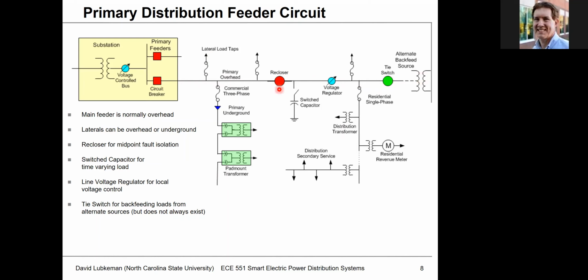I've also shown in this diagram a switched capacitor bank, used for power factor correction and helping to control voltage, as well as a voltage line regulator. A lot of times I'll call these devices outside the fence line voltage regulators, to be clear they're mounted up on poles as opposed to the devices in a substation.